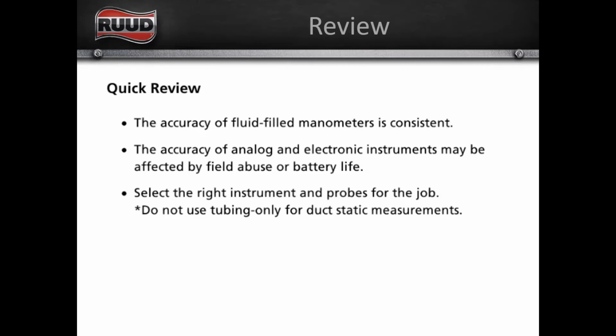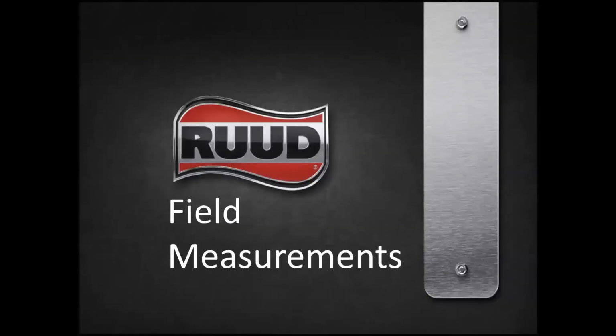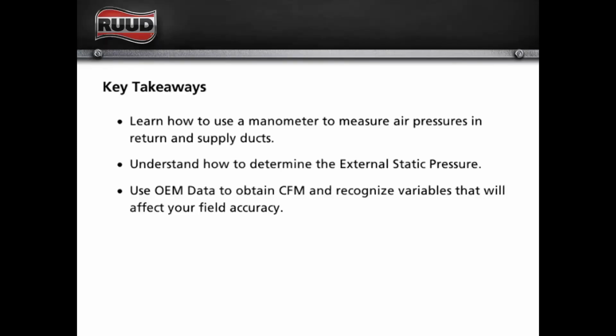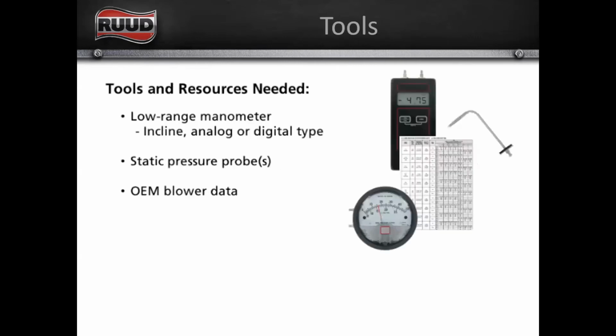If you don't have a manometer, and that's not part of your toolkit that you're carrying around with you every day, you need to get one. I can't stress that enough. You don't have any idea how much air you're moving if you're not checking static and comparing it to the blower table, which I'm going to show you in a minute. So field measurements, we're going to learn how to use the manometer. We're going to check air pressure. We're going to determine static, and then we're going to use our blower data to obtain the cubic feet per minute that we're moving through this ductwork.